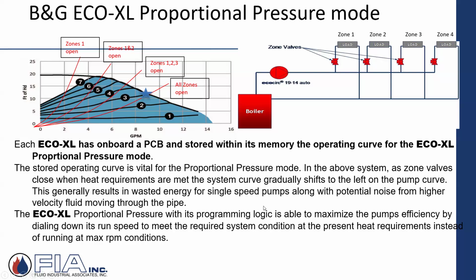What I have over here is the pump curve that's selected to operate in proportional pressure. All it's saying here is with all 4 of these zone valves open, maybe I'm operating on curve 3. As one of those zones closes, what the pump would normally do is want to back up on the curve, like we talked about earlier on a constant speed. But because the pump has all of the performance points, flow, wattage, RPMs mapped in that software, as it starts to move, it says, wait a minute, you're moving off of that curve 3 set of conditions. I'm not going to let you back up.